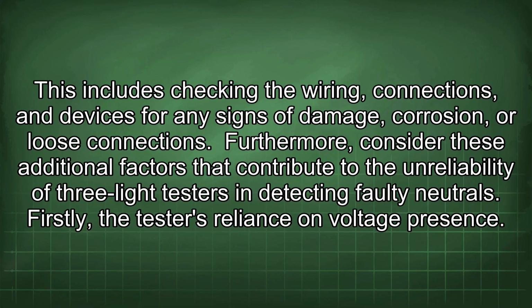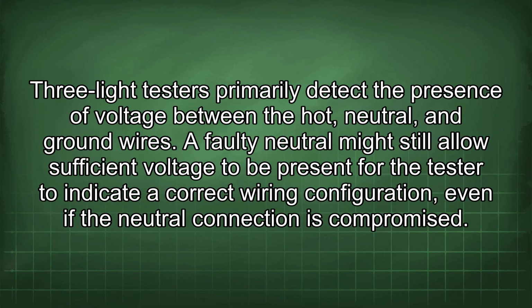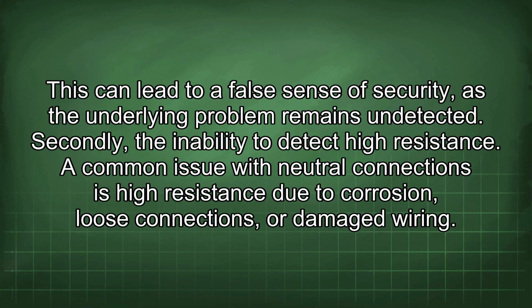Furthermore, consider these additional factors that contribute to the unreliability of 3-light testers in detecting faulty neutrals. Firstly, the tester's reliance on voltage presence. 3-light testers primarily detect the presence of voltage between the hot, neutral, and ground wires. A faulty neutral might still allow sufficient voltage to be present for the tester to indicate a correct wiring configuration, even if the neutral connection is compromised. This can lead to a false sense of security, as the underlying problem remains undetected.